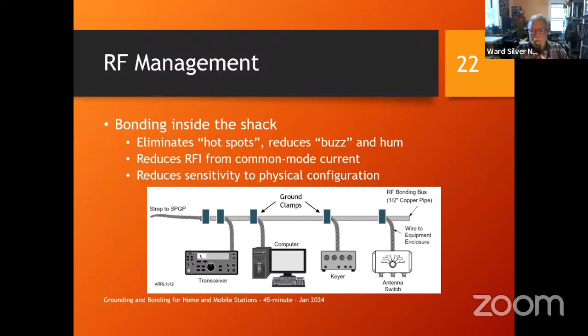So the idea is to reduce RFI from this common mode current that is picked up and conducted on all the cables. If you don't have voltage differences, you won't have current flow. And this also reduces sensitivity to how your station is assembled. So you don't get into a situation where, to operate 15 meters, I have to sit over here and I can't put my feet on the floor and I have to hold one thing or I get an RF burn. No, this makes it all one electrical thing. That's what bonding does for you.